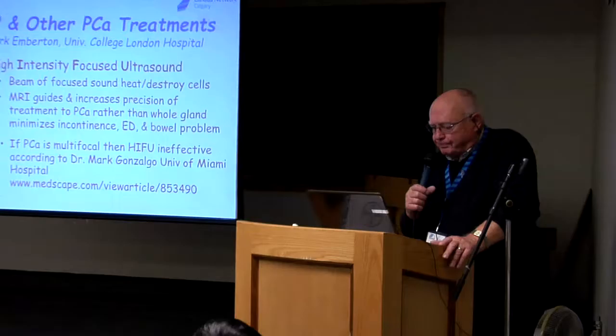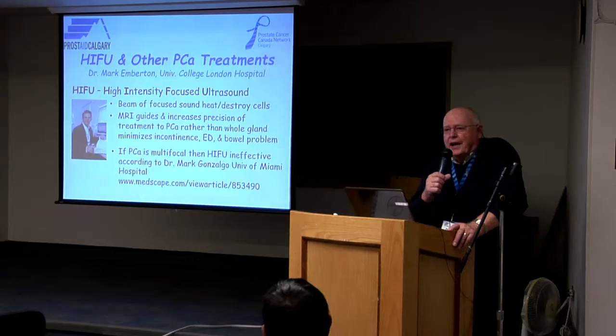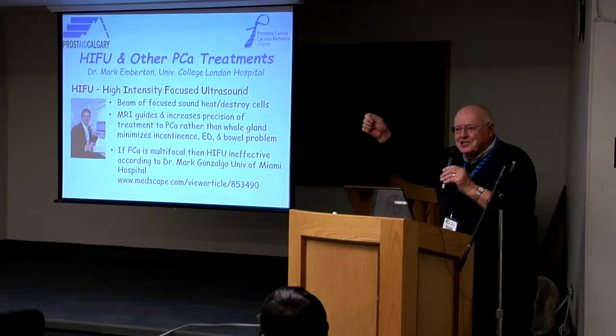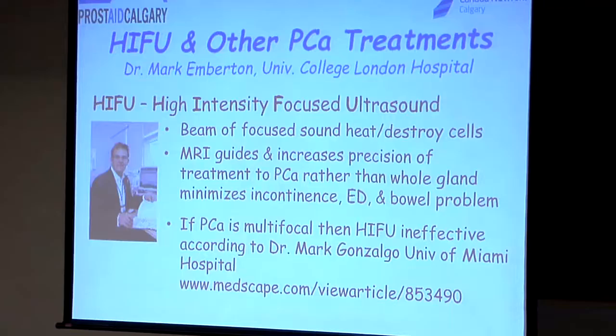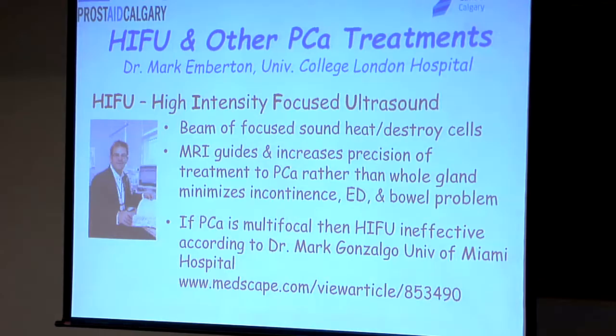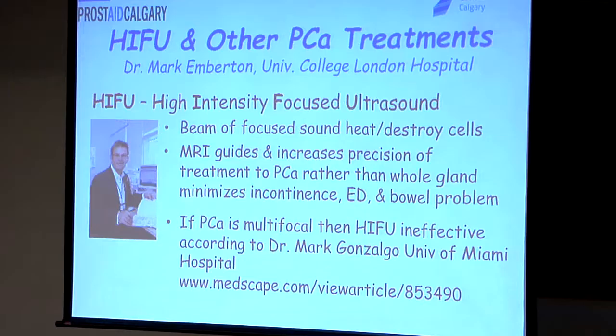My talk is about HIFU, high intensity focused ultrasound. I'm sure all of us, when we were kids, would get a magnifying glass and the sun's rays and some tissue paper, and we'd hold the glass up and get that light to focus on a particular point on the paper, and if we were successful, the paper would ignite. Well, that's really what's happening here, only instead of using light, they're using sound. It's a somewhat similar principle in the sense that it's focused, and focused on the tumor within the prostate gland.